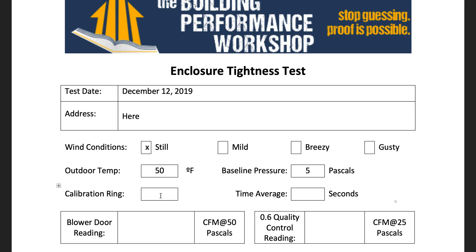The calibration ring — let's just say that you went open — and that's the configuration of the blower door fan itself, how many rings are in place. You've generally got wide open fan, you've got A, you've got B, you might have C, you might have B4 if you're using a 5000 model from Retrotec. The time average: generally 10 seconds is a good even number to go with. That basically means that the blower door system is going to be averaging the reading over the last 10 seconds into one number, updating every second.